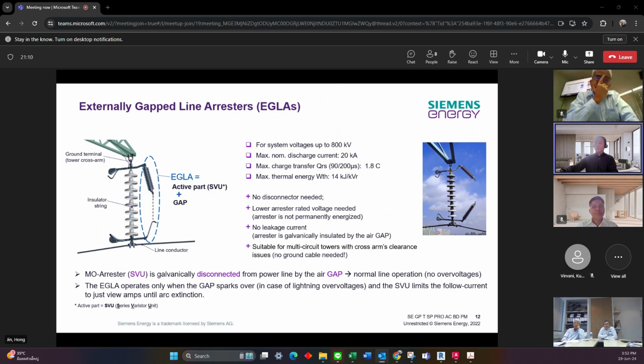So, moreover, we need to talk about EGLA. So EGLA, for this picture you will see we have active part SVU plus one gap. And the EGLA can also be used for voltage levels up to 800 kilovolts. So this is our standard configuration. It can be designed for 20 kiloamps discharge current. And also the charge transfer QRS will be 1.8 coulomb for the normal operation case. And the thermal energy WTH will be 14 kilojoule per kilovolt.